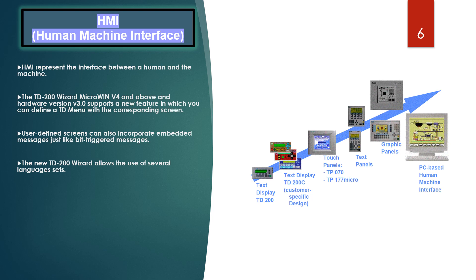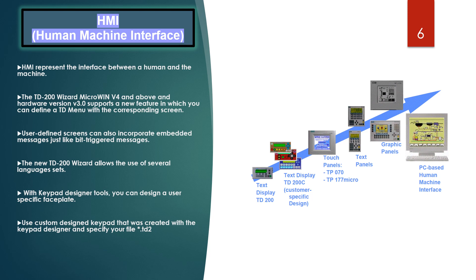There is also a very interesting tool: the Keypad Designer. With this tool you can design a user-specific faceplate for the TD200 C, freely choosing the assignments, colors, and functions of buttons. The tool is installed with Step 7 Microwin and can also be used independently of the programming software. It outputs a file with the extension *.td2 containing the data for the faceplate. To use it, select the option 'use custom design keypad created with the Keypad Designer' and specify your file with extension *.td2.